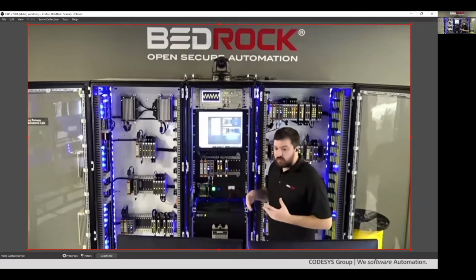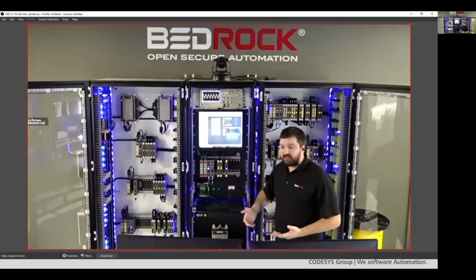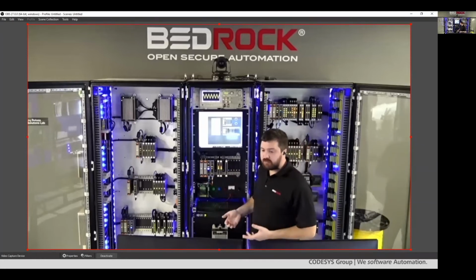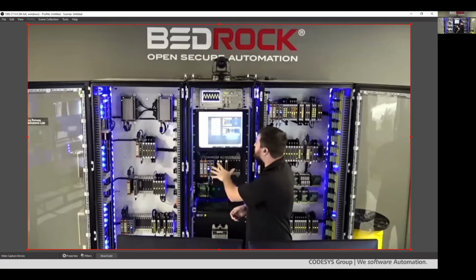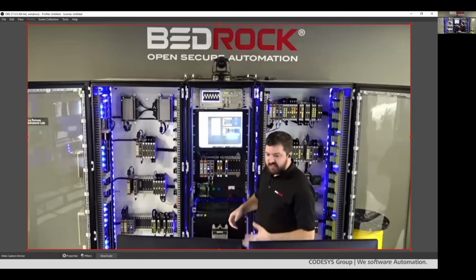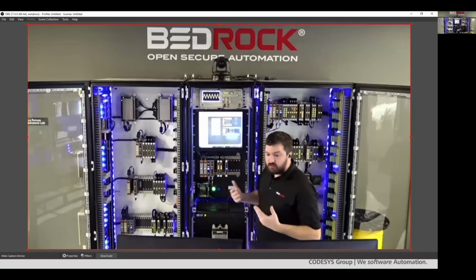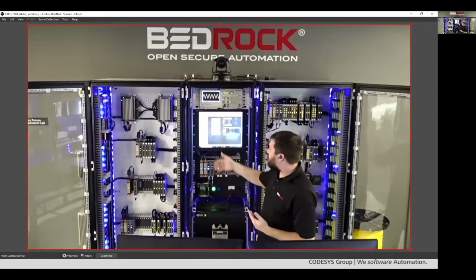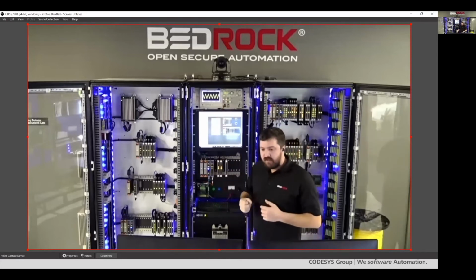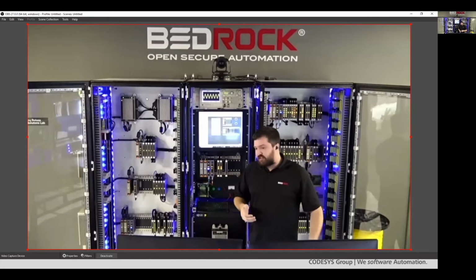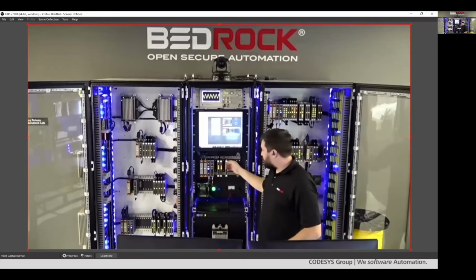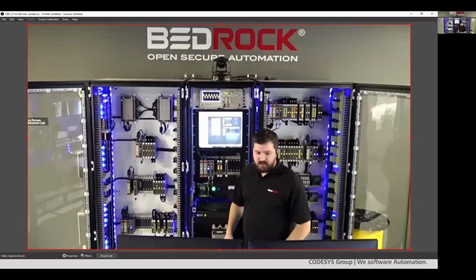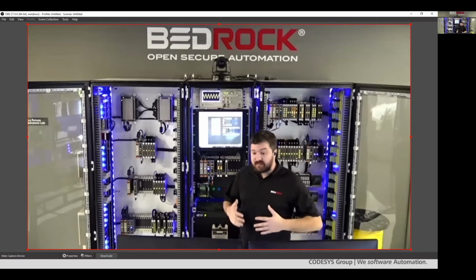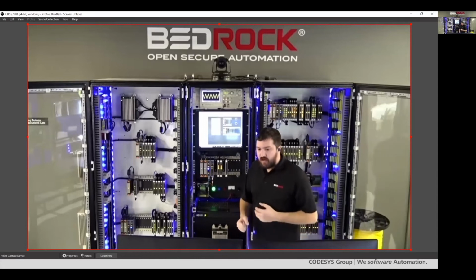So with the full implementation of redundancy, thanks to the tools available in CODESYS, you can make a very rock solid system. And as you see, as I made these changes, you never lose your process data. This is just one single analog output, but it doesn't matter—it takes all your digitals in, digital outs, analog in, analog outs, all your field bus communication if that's going through a communication module. So you can really make a zero downtime system on top of the control system.